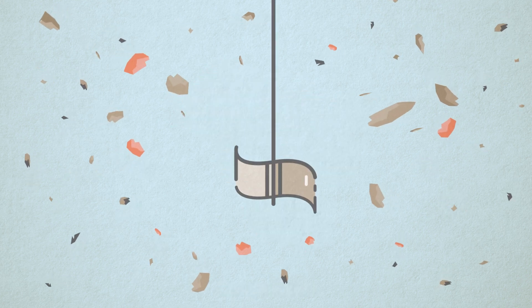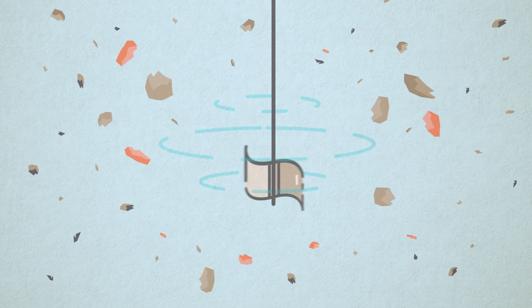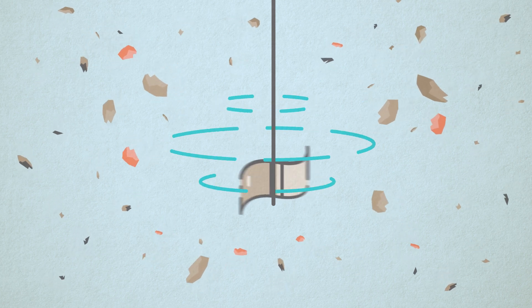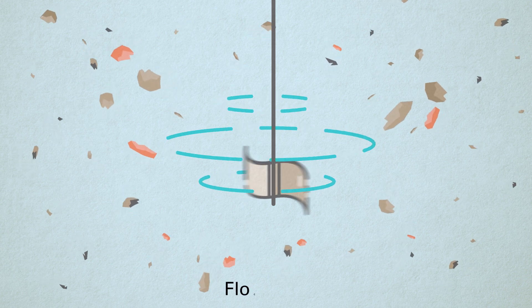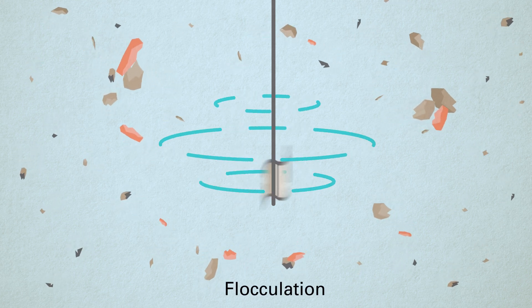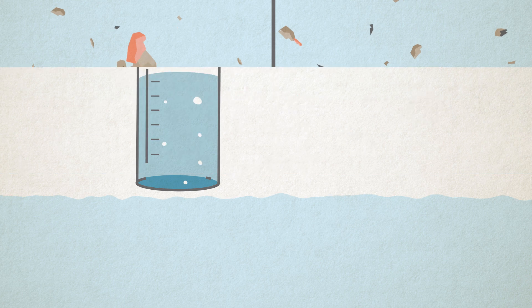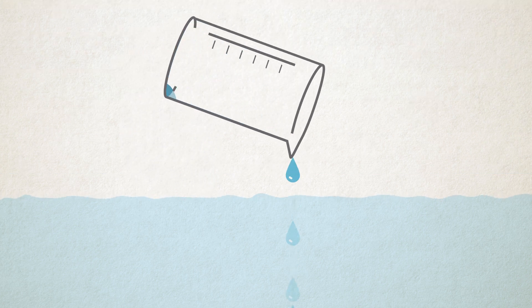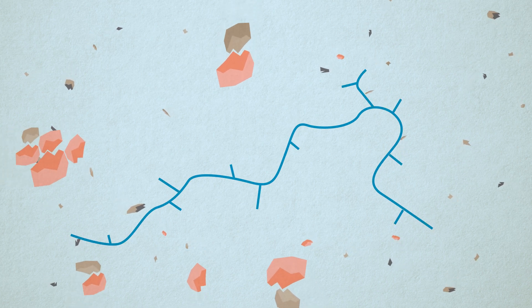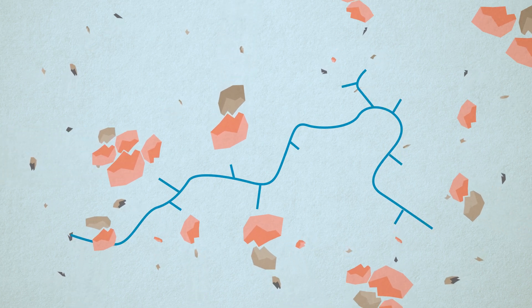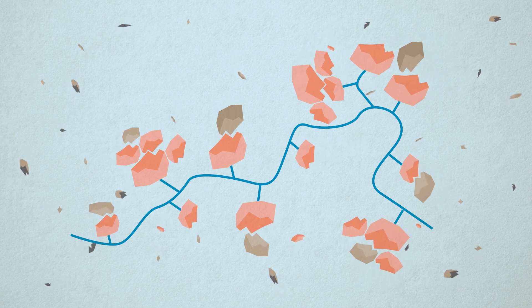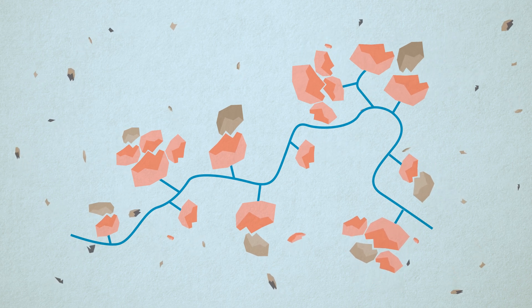We use a giant stirrer to mix the coagulant into the water quickly, which encourages the colloids to bump into each other and start to stick together. This rapid mixing is flocculation. To get the particles to become even bigger and stronger we add a polymer. The polymer grabs onto the group of colloids, clumping them together to form a floc. This floc can easily be trapped in our filters and removed from the water, reducing its turbidity.